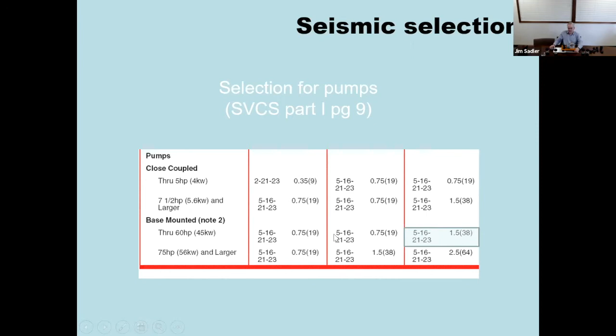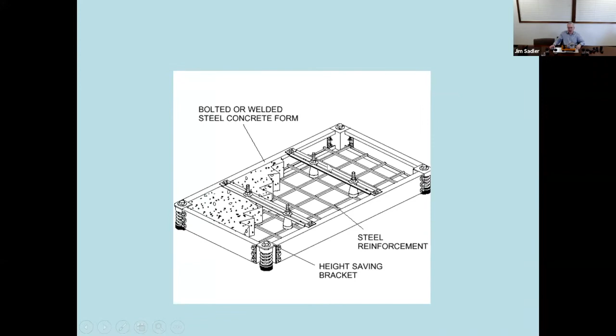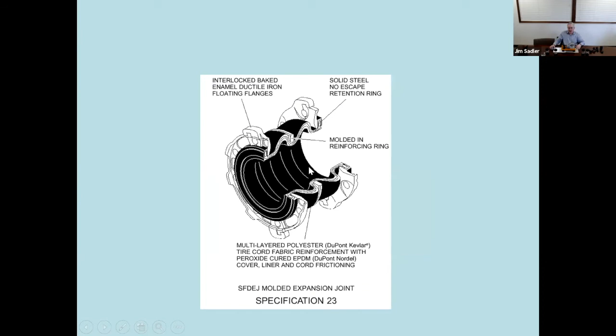Well, we're going to have numbers instead of letters to designate the equipment we recommend. And in this case, it's 5, 16, 21, and 23. Those correspond to the products, which I'll show you in a moment. And then again, to the right of that is the recommended static deflection of the isolator. So again, same spring, that hasn't changed. Same concrete base, that hasn't changed. Same flex connector, no change there. The only thing we've added in a seismic zone is a seismic snubber.